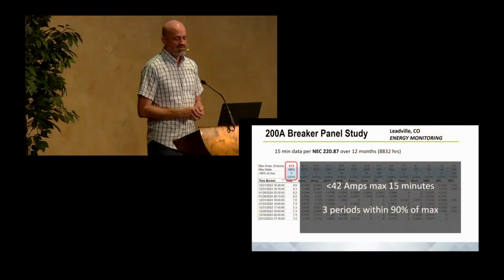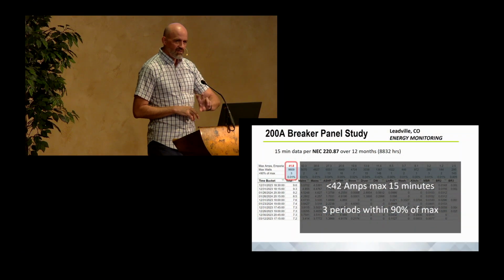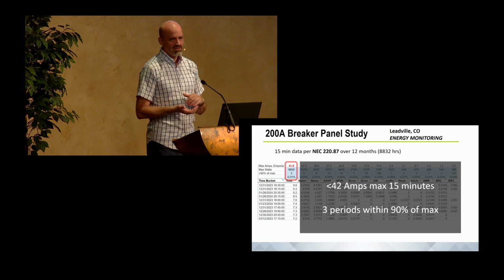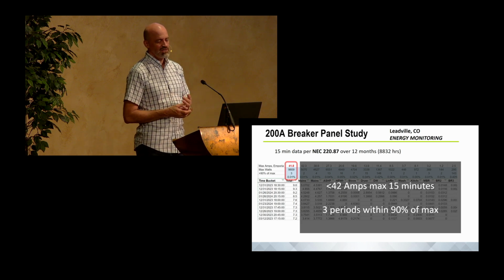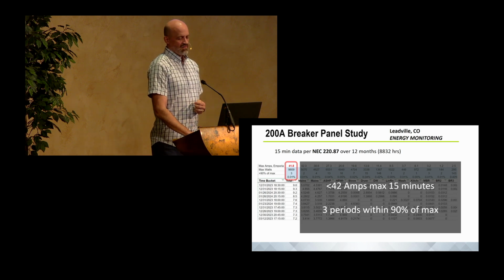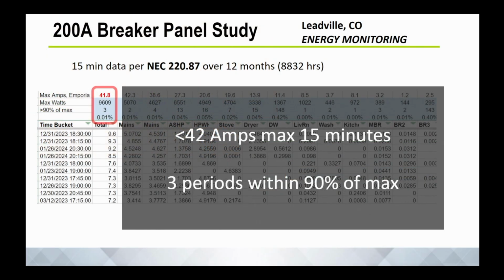They were required to put in a 200 amp panel because it's relatively new construction, 3 years old now. On that panel—to be fair, they're not there all the time, but when they are, they're fully there, heating, skiing, doing all the things—their worst 15 minutes was 42 amps out of the 200 required by code.